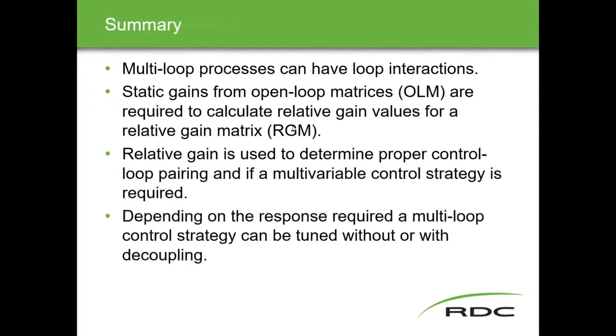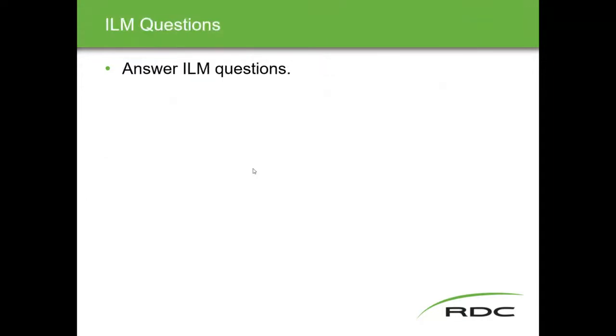In summary: multi-loop processes can have loop interactions and most often do. Static gains calculated from open loop matrices are required to calculate the gain values for the RGM. The RGM is used to determine proper control loop pairing and the severity of interaction, telling us whether we need a multi-variable strategy. Depending on the response required, a multi-loop strategy can be tuned with or without decoupling. This is probably the most difficult ILM in advanced process control, which is why it's covered third rather than first.